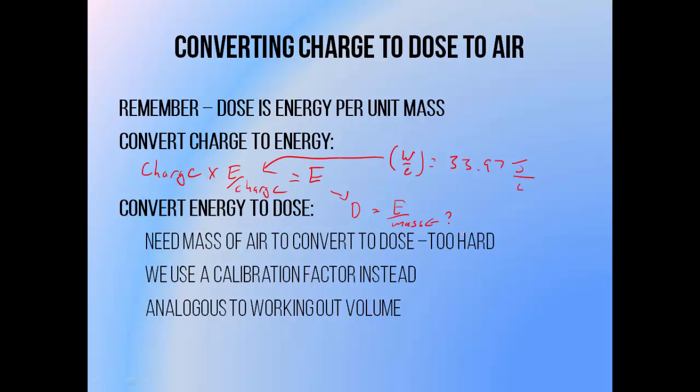This is how it's actually done at some primary standards labs that use cavity ionization chambers with a known volume. But unfortunately it's difficult to accurately measure the volume of clinically used ionization chambers, so we find that using a calibration factor is a more accurate method.